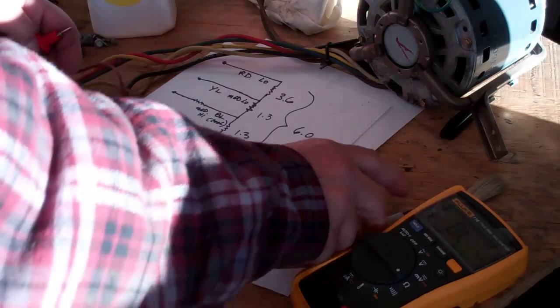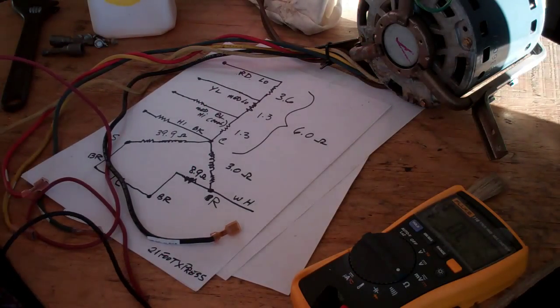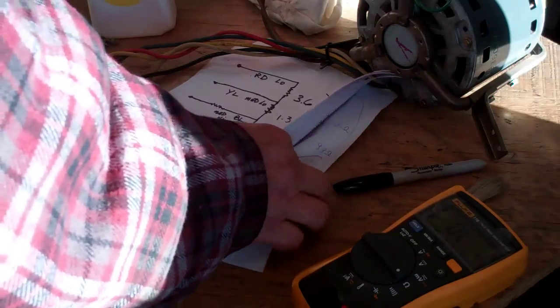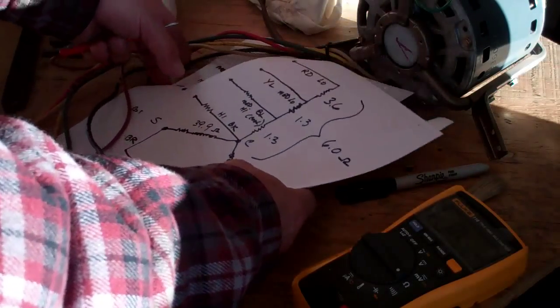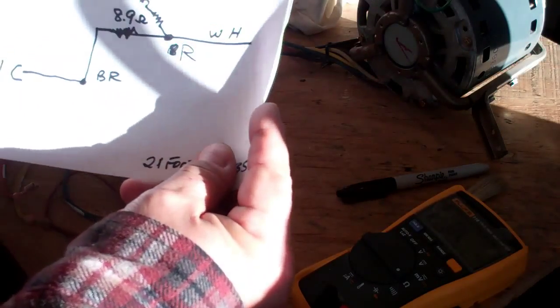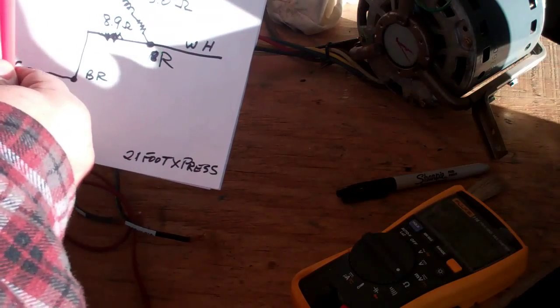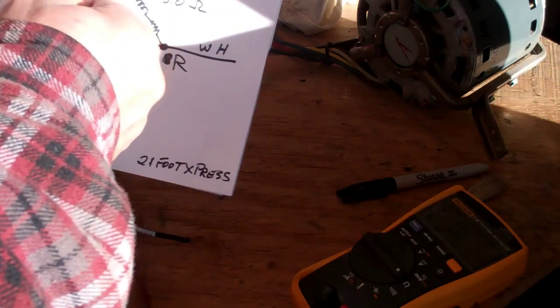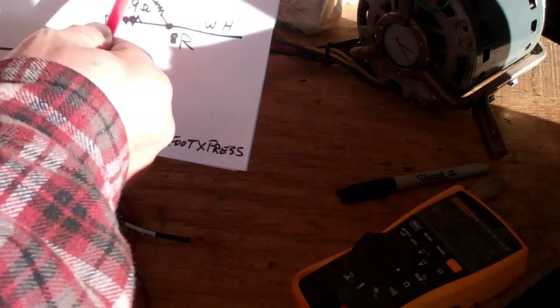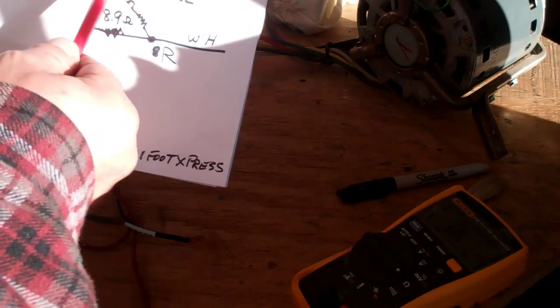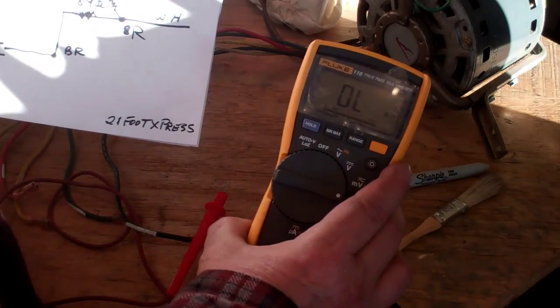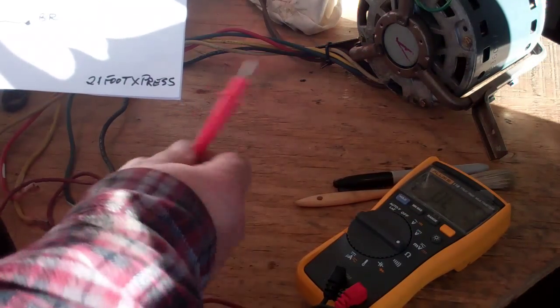So that quickly you check the winding on the motor and determine that there are no shorts to ground. There are no opens in any of these lines, because instead of getting a resistance value, you'd get 0 or open line, what it's showing right there, OL, or infinite resistance.